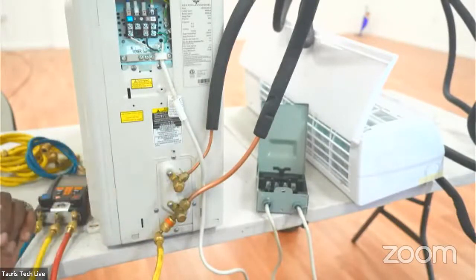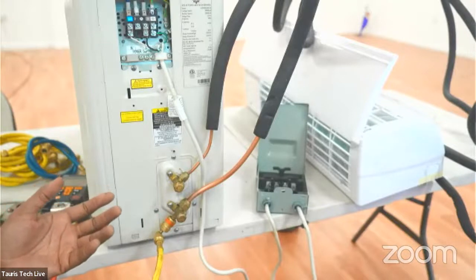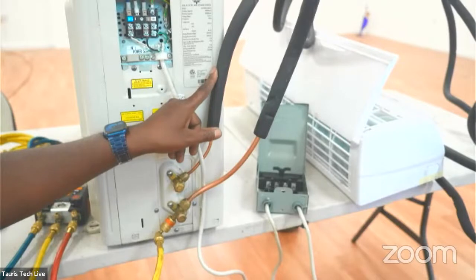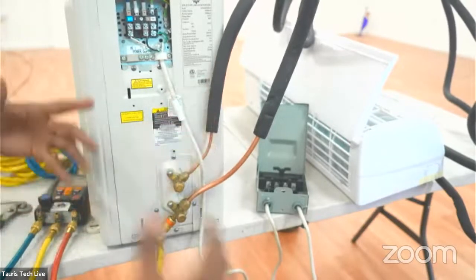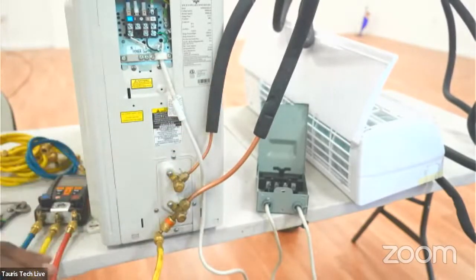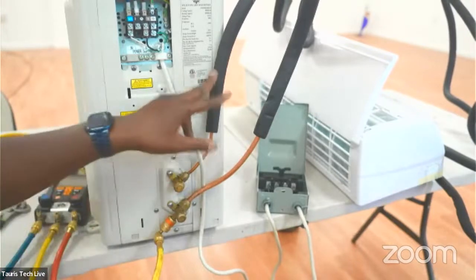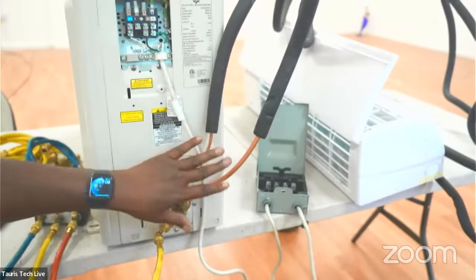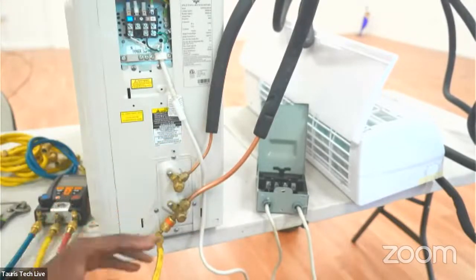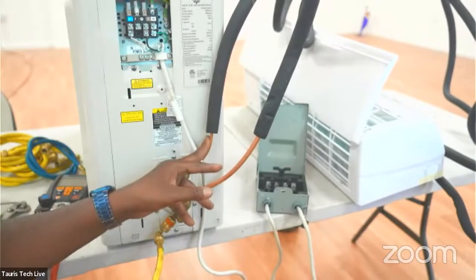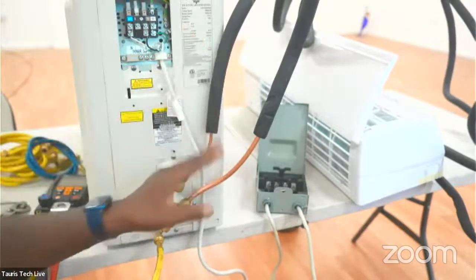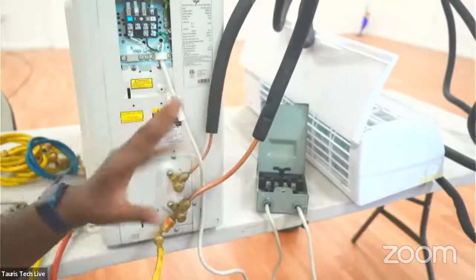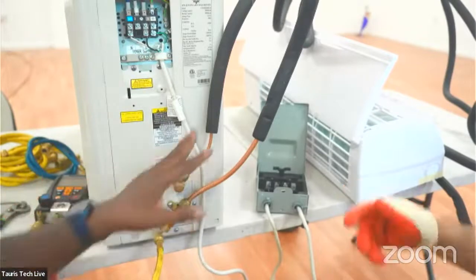Now, if you look at a central air conditioning unit, you will never see insulation on the liquid line. Central air, when they have the square, if you have ducts in your house, they never have this because it's always high pressure liquid. Because it's high pressure liquid, it's always hot. I don't have to worry about condensation. So this is not insulated. The suction line is always insulated because the suction line is always cold. But with this one, because it switches, you have to have insulation.